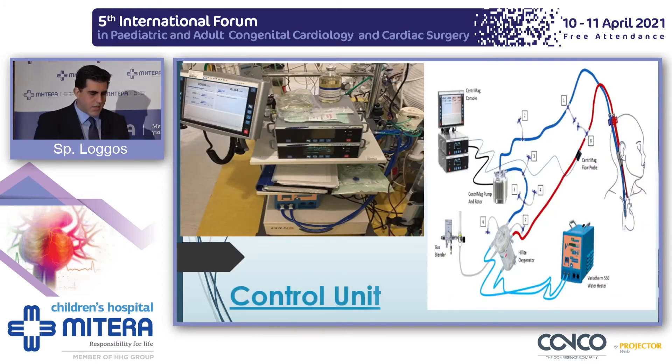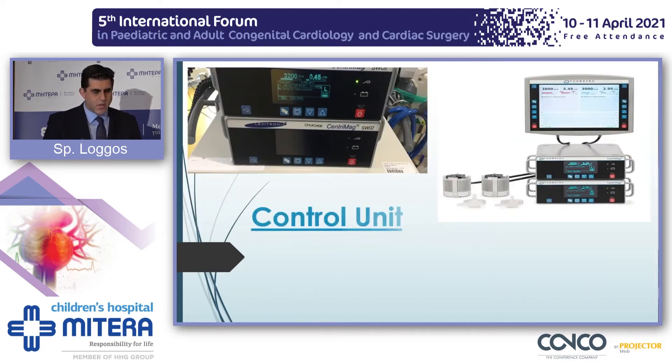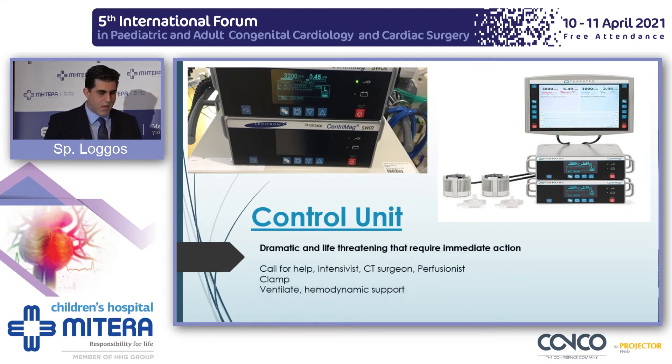This is a CentriMag Maquet control unit, and you can see there's always redundancy — two consoles and two magnetically levitating pumps. If one fails, you can switch to the other. It could be dramatic; you need to call for help, clamp, and by all means ventilate and provide hemodynamic support of the patient.